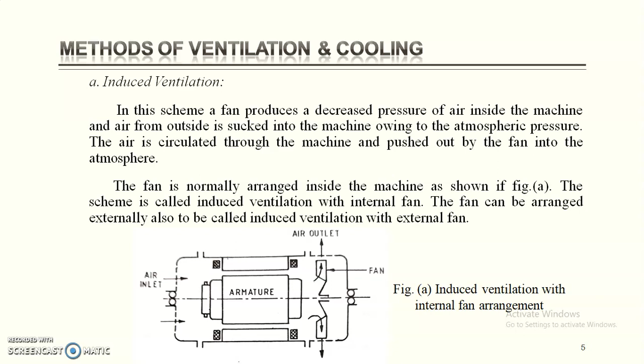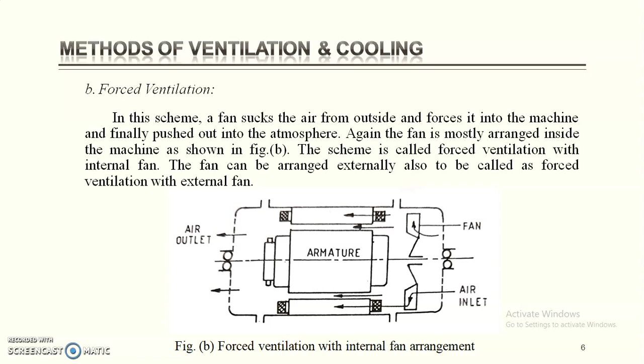Forced ventilation. In this scheme, a fan sucks the air from outside and forces it into the machine, and finally it is pushed out into the atmosphere. What is the difference between induced and forced? In induced ventilation, the low pressure is created by the fan, but in forced ventilation, with the help of the fan, air is forcefully pushed in from one end of the machine. That is the main difference between them. Again, the fan is mostly arranged inside in this system also. As shown in the figure, this is forced ventilation with internal fan. It can also be arranged externally, which is called forced ventilation with external fan.